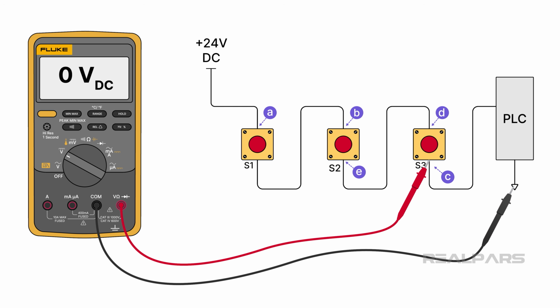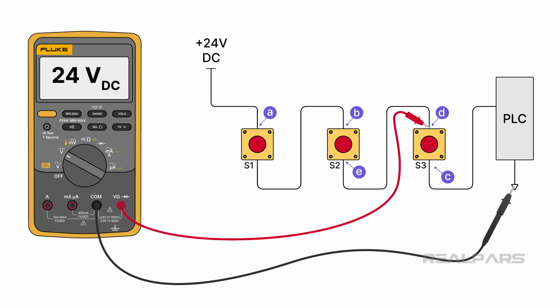It could be S2, S3, or a broken wire or a bad connection. Now it's a matter of taking voltage readings at points D and E to pinpoint where the 24 volts DC disappears. Let's assume you measure 24 volts DC at point D. That measurement would lead us to conclude that S3 is open, which is a pretty solid assumption.